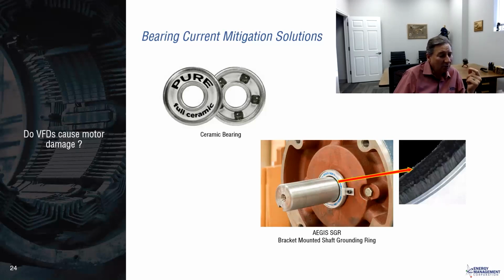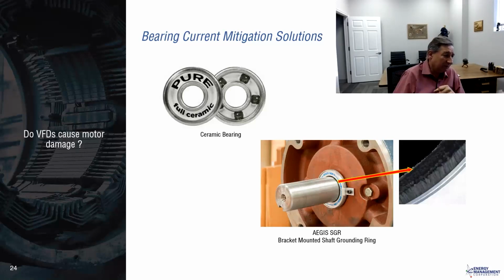And when you go back and look at the NEMA MG1, they'll say there's not enough conclusive evidence to really give a definite recommendation what to do, because applications vary so much. There's so much variety to it. But they say right in NEMA MG1 that they are seeing shaft voltages from 10 volts to 40 volts. And those clearly are causing damage. When we do our testing, we typically consider something under 5 volts as not being consequential to what we'd expect to be a lot of damage.